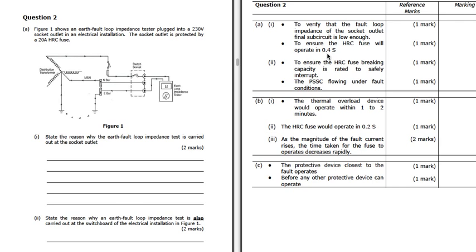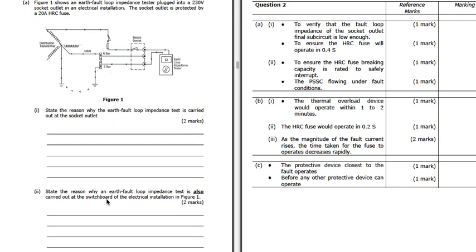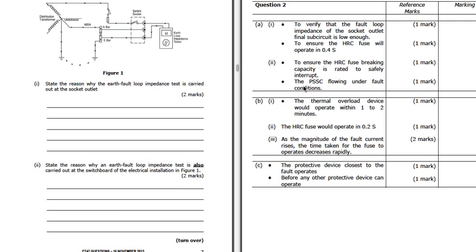Now, if we carry it out at the switchboard, what are we looking for there? We're looking to make sure that the breaking capacity is rated to safely interrupt the prospective short circuit current flowing under fault conditions. So we're making sure that the HRC fuse has a high enough breaking capacity.